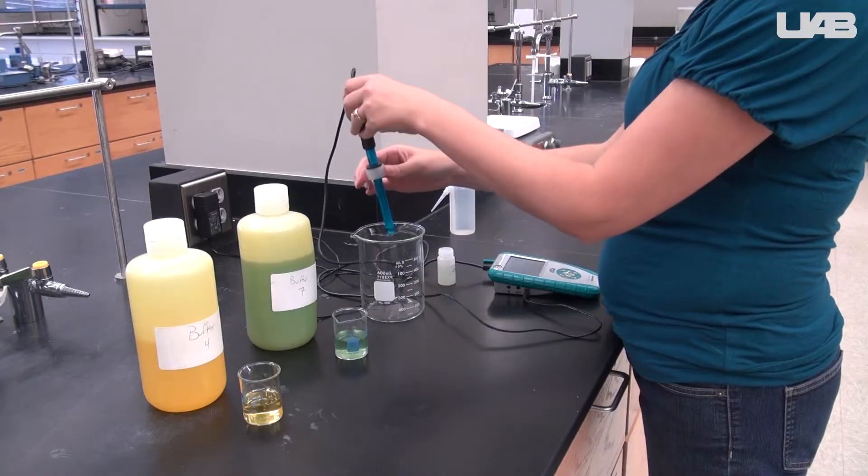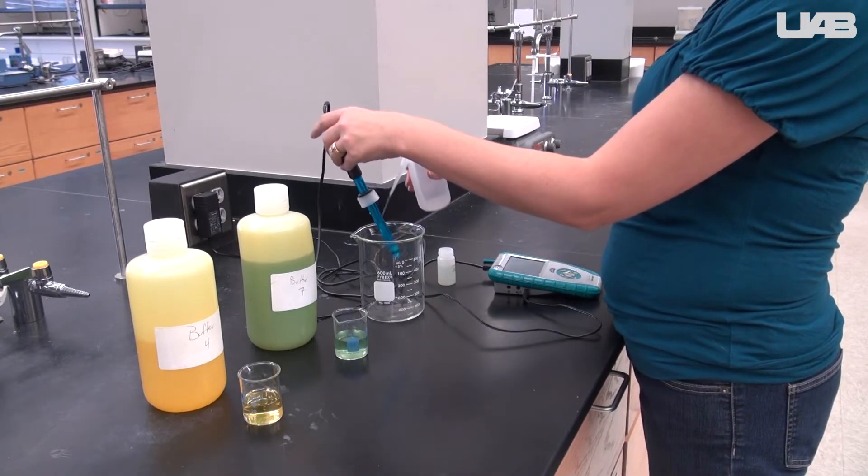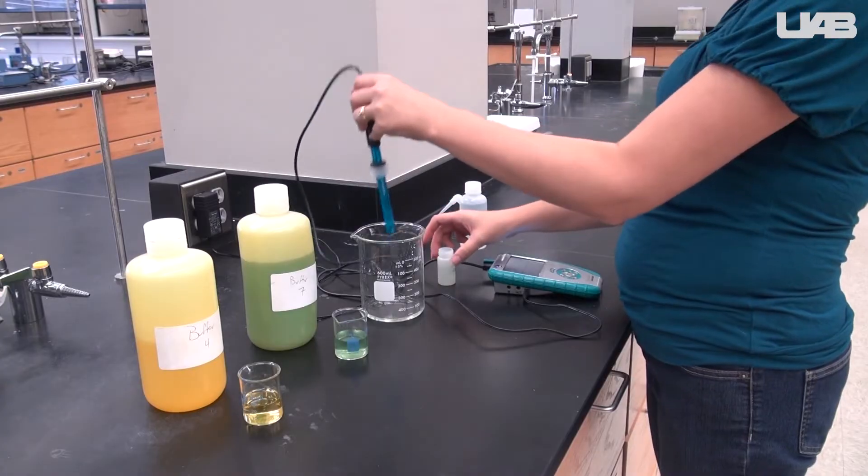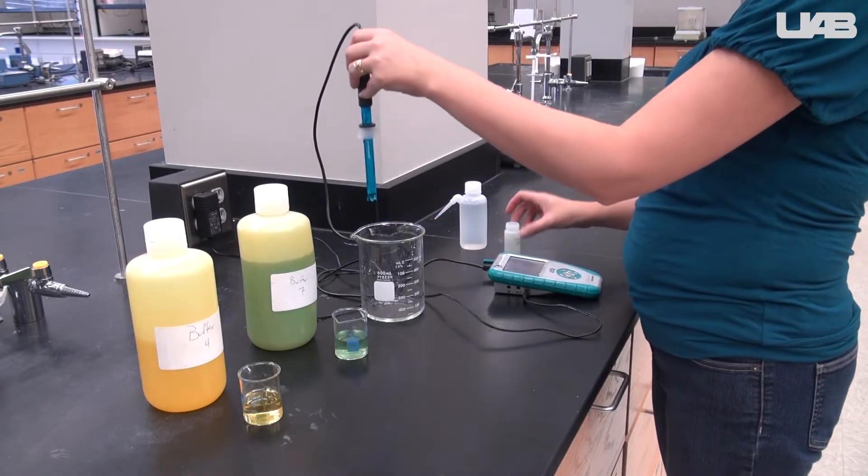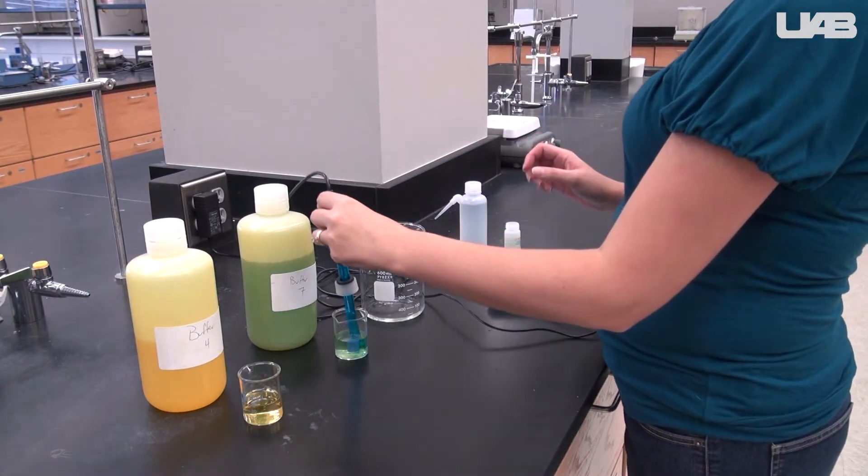Rinse the pH meter off using your wash bottle as you hold it over the waste beaker. Give it a gentle shake to dislodge some of the water droplets and place the probe in the pH 7 buffer.